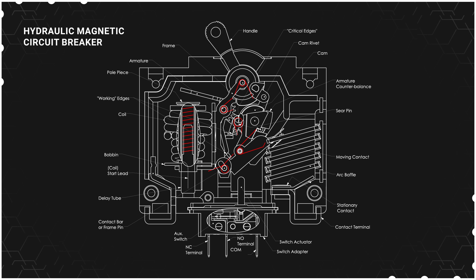A hydraulic magnetic circuit breaker operates on the solenoid principle. It features a movable delay core held with a spring and dampened with a fluid. Current flows through a coil, generating magnetic flux that moves the delay core against the pole piece, increasing the magnetic flux enough to rotate the armature and open the breaker.